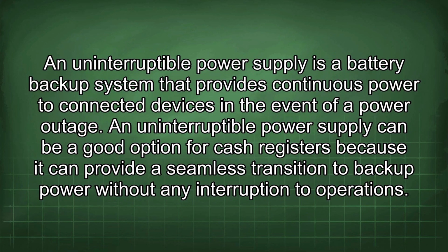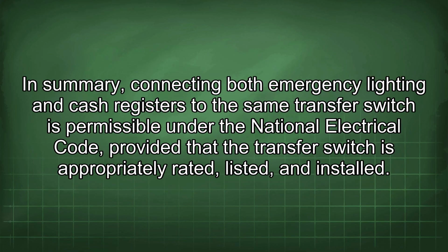An uninterruptible power supply can be a good option for cash registers because it can provide a seamless transition to backup power without any interruption to operations. In summary, connecting both emergency lighting and cash registers to the same transfer switch is permissible under the National Electrical Code, provided that the transfer switch is appropriately rated, listed, and installed.